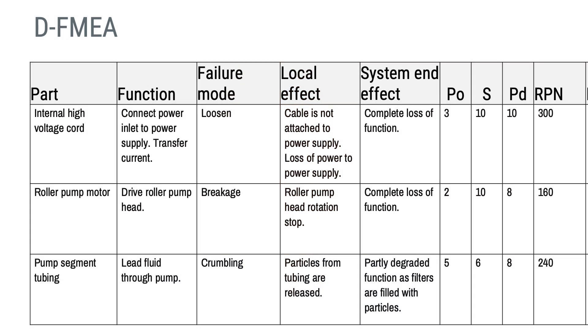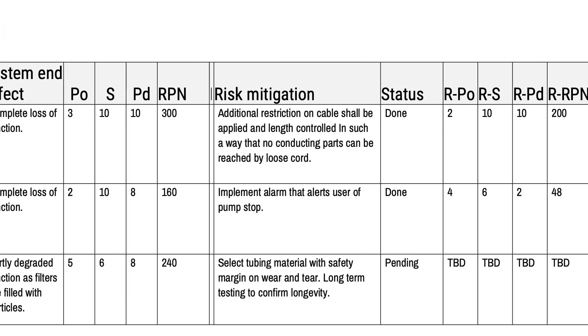This is what FMEA could look like. In this example you can see a design FMEA, or DFMEA. The DFMEA looks at components and what failure of such components would lead to. In this example you can see how design choices or design failures lead to a breakdown of system performance. The risk is measured using an RPN number, which is short for Risk Priority Number. The highest-ranking risks should be addressed first by mitigations, and just as in the case of ISO 14971, the residual risk is estimated again at the end using the same technique.